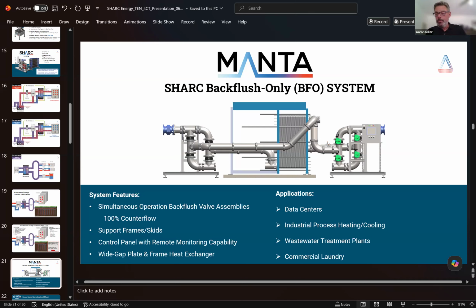And long story short, if you can guarantee us that your water loop doesn't have anything in it bigger than 2.5 millimeters, we don't need that fancy basket filter. We don't need the macerator. We really just need our heat exchanger, right? With specialty piping and valve on either side, and the control that looks at backflow pressure, back pressure differential, temperature, flow, and it basically will continually back flush the system to keep it cleaning itself while you're getting maximum thermal transfer. It's got clean in place ports built right into it.